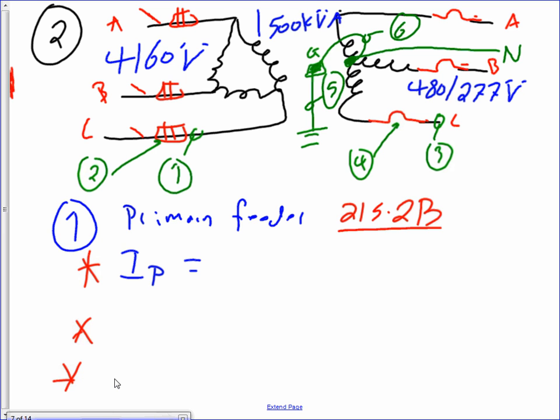You guys have it in front of you, right? Everybody has it? Look at this baby. This baby is 4,160 volt on the primary side, delta. On the secondary side, I have 480Y/277 instead of 208Y/120. The transformer is a 1500 kVA transformer, big boy. And I am to size the same thing: the feeders on the primary and the secondary, the overcurrent protection device on the primary and the secondary, the main bonding jumper on the secondary, and the grounding electrode conductor on the secondary side.